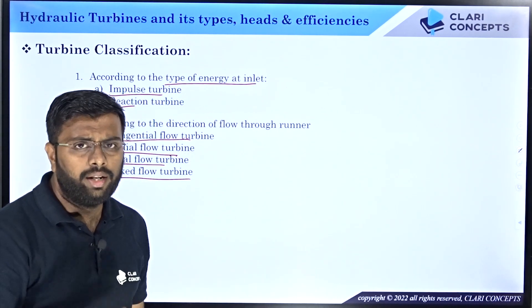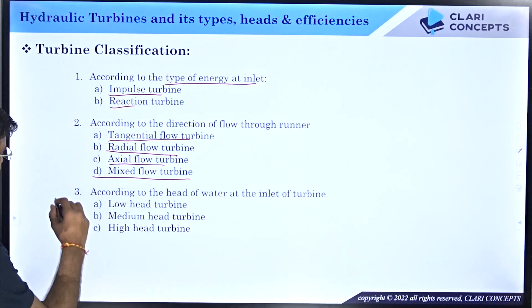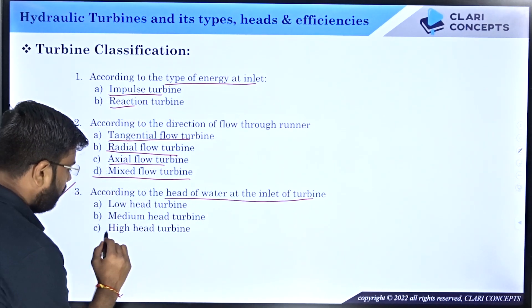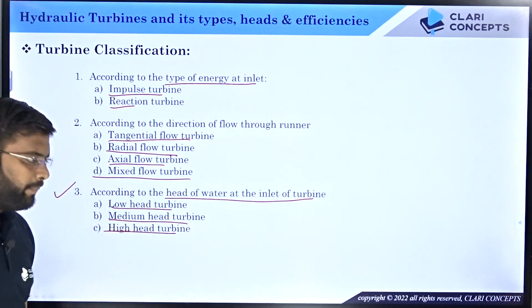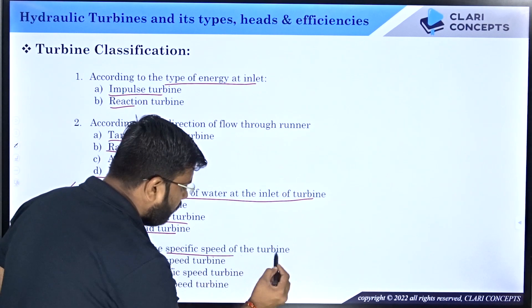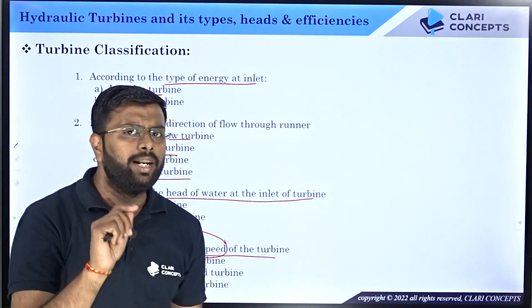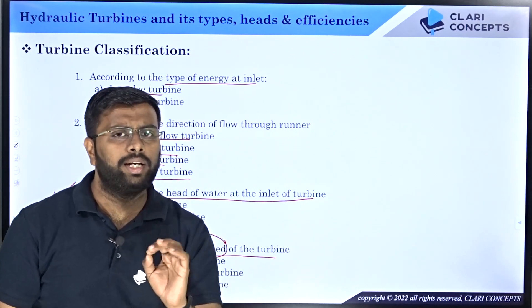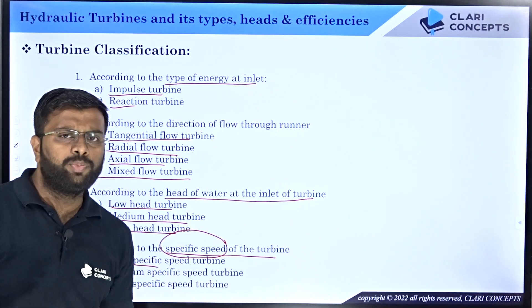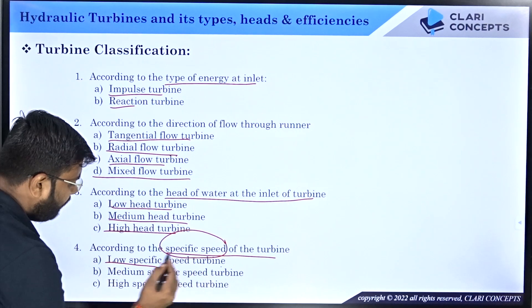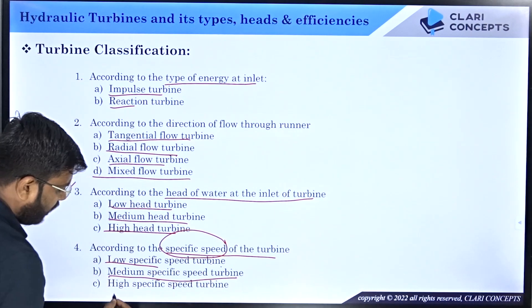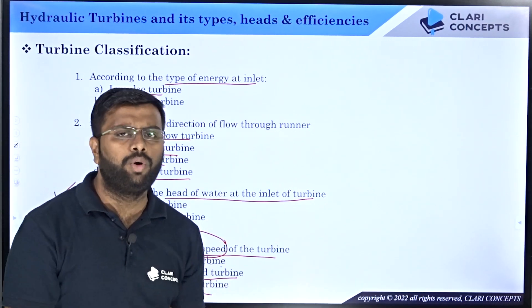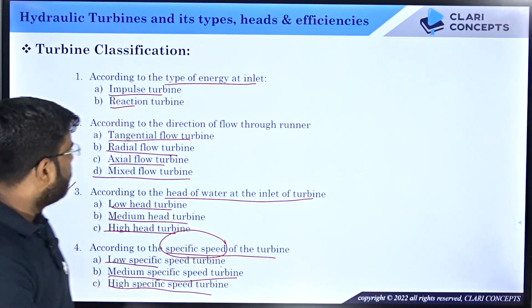The third classification is according to the head of water available at the turbine inlet: Pelton is a high head turbine, Francis is a medium head turbine, and Kaplan is a low head turbine. The fourth classification is according to specific speed. Specific speed relates to the best performance of a turbine. Pelton gives its best performance at low specific speed, Francis operates at medium specific speed, and Kaplan at high specific speed. We will cover specific speed in a dedicated lecture.